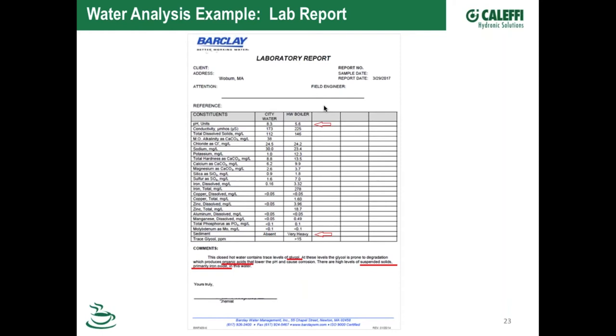You can see the pH here is a little low. Why would the pH be that low? Well, it did have some glycol in it at one point, and when glycol goes bad, that's a primary indicator that it's been burned or overheated, or that the pH has been compromised by a dirty fluid or something else in the system. That's the note he put on there - why is the pH of the system so low? If it's just city fill water, then something else is going on with the system that you need to get to the bottom of.